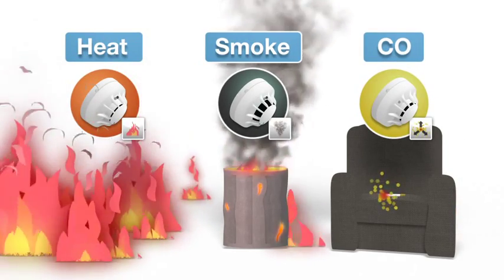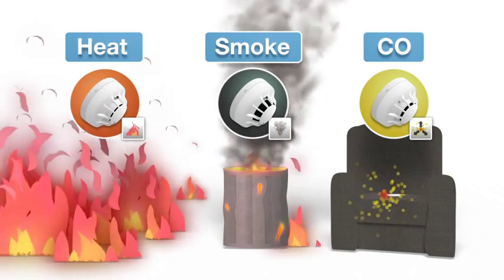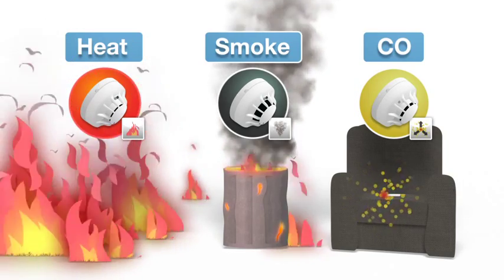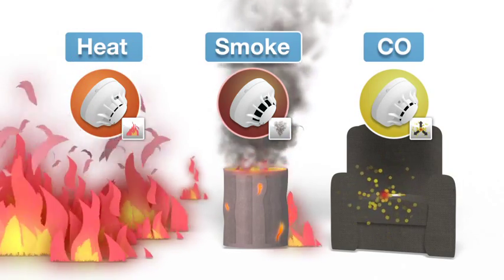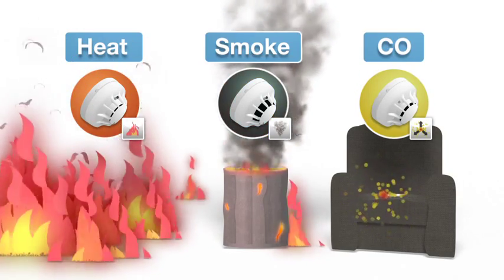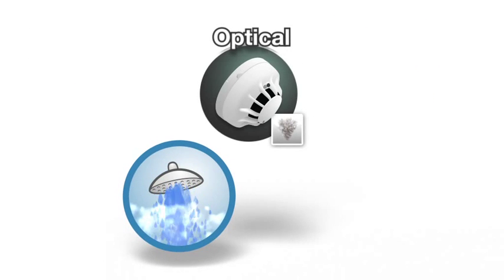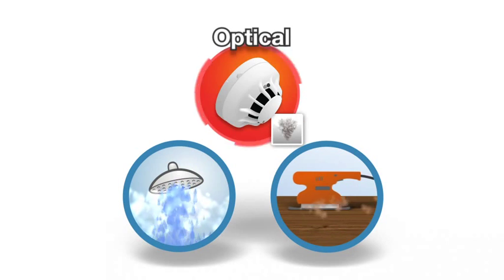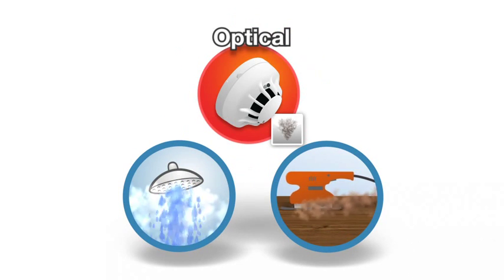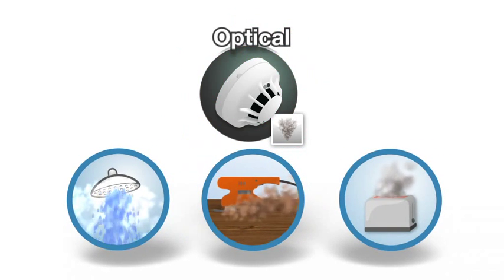As single sensors can only react to one indicator of a potential fire, the risk of false alarm is high. In the case of optical sensors, steam and dust clouds can be misread as smoke, as can other temporary indicators such as burning food.